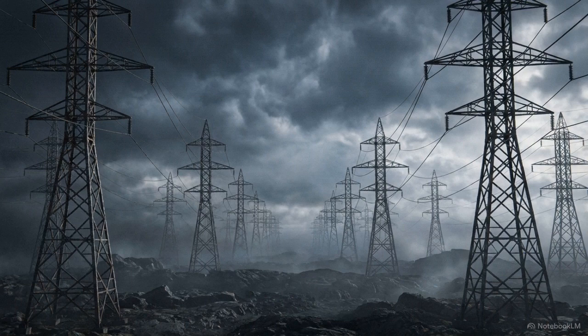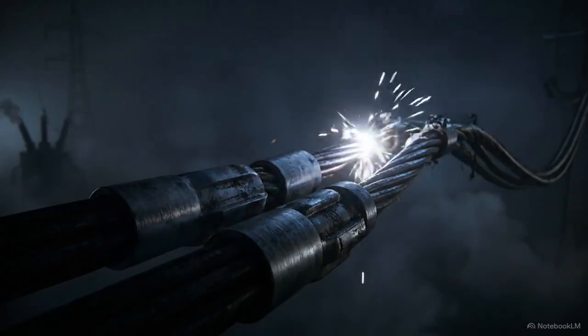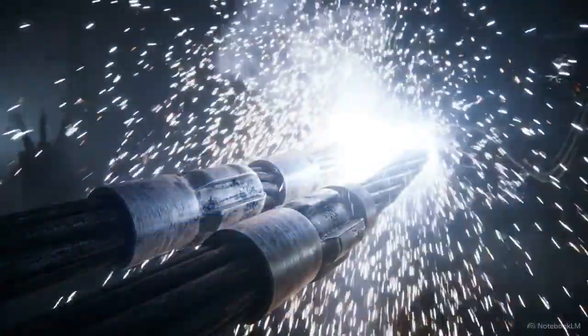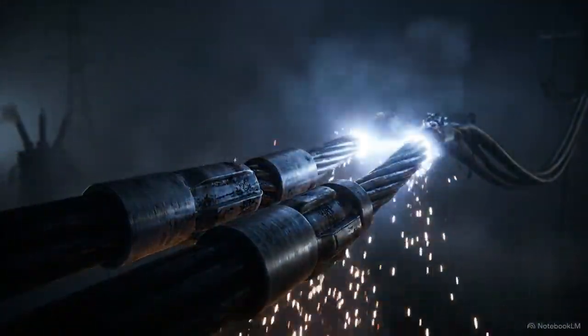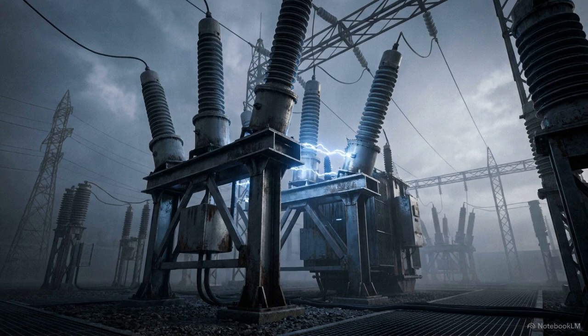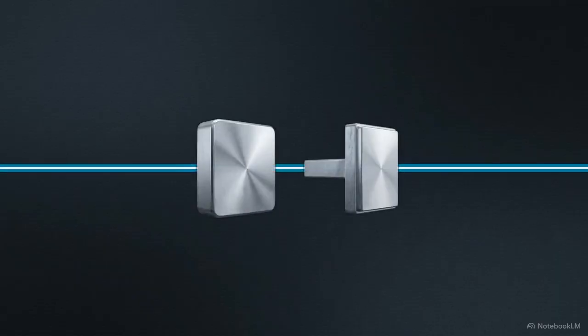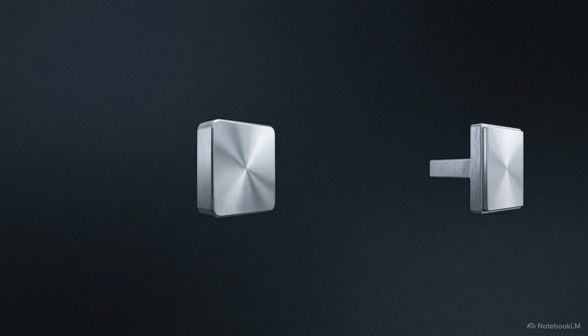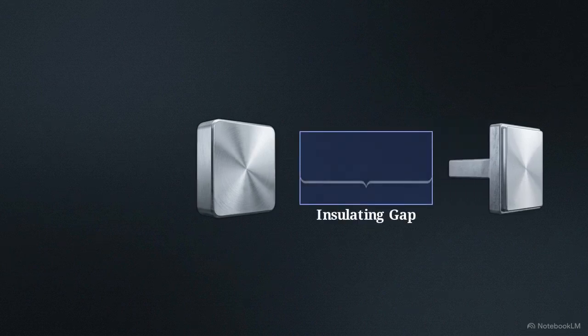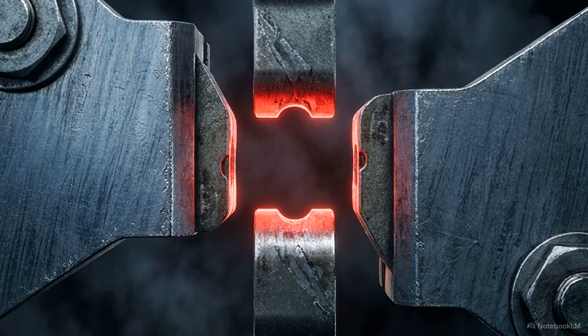The modern power grid moves an immense amount of energy. When a fault occurs on the line, that energy turns destructive, sending a violent surge of current through the system. The primary defense against this surge is the circuit breaker. Its job seems simple: physically pull two metal contacts apart to break the circuit. But opening the breaker doesn't immediately stop the fault.